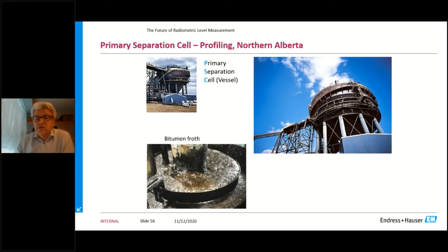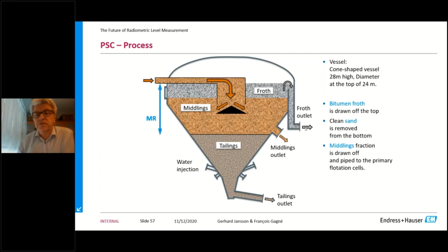These are primary separation cells, probably something like 25-30 meters high. The customer wanted to measure the interface across the whole height of the vessel, because at the bottom there's what they call tailing, which is sand and water and so on that they don't really want. There's middling, which is the incoming material from the oil field, and then they inject air and so on, and get froth that skims over, and then the output, which is in principle the oil.